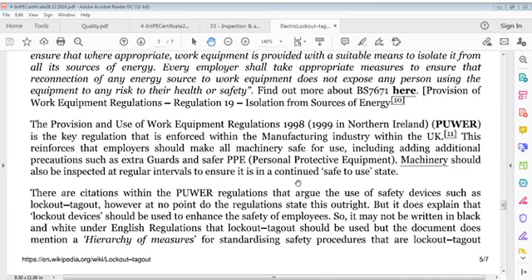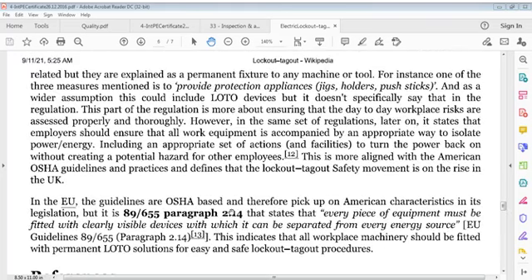There are citations within the PUWER regulations that argue for the use of safety devices such as lockout, tagout. However, at no point do the regulations state this outright. But it does explain that lockout devices should be used to enhance the safety of employees. So it may not be written in black and white under English regulations that lockout, tagout should be used, but the document does mention a hierarchy of measures for standardizing safety procedures that are lockout, tagout related.